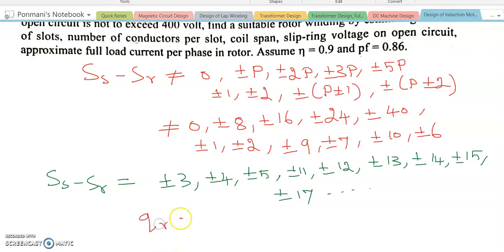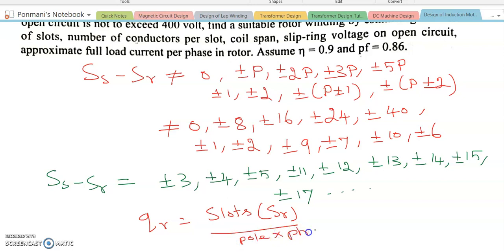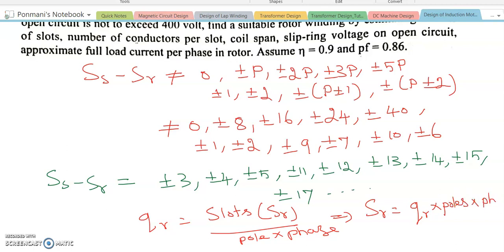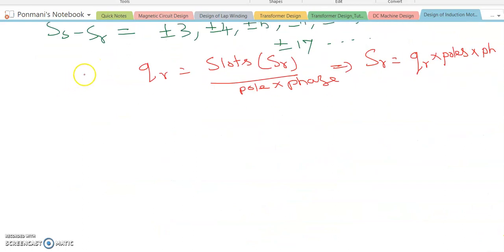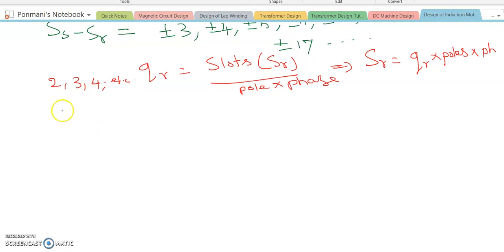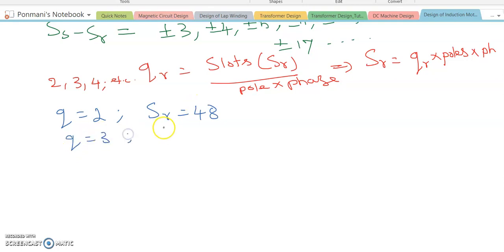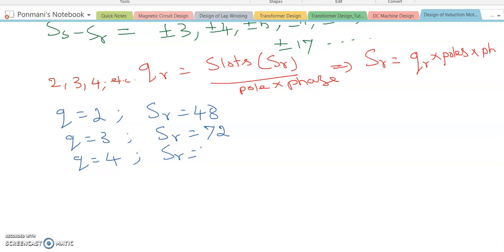Let QR be the rotor slots per pole per phase. Then the rotor slots SR equals QR multiplied by total number of poles multiplied by 3. For QR equal to 2, SR becomes 48. For QR equal to 3, SR becomes 72. For QR equal to 4, SR becomes 96, and so on.